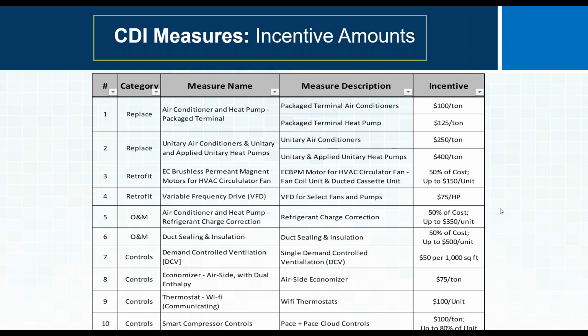The measures 5 and 6, the O&M measures, we can correct the charge on the units. One of the benefits of the PACE control we'll be hearing about is that it provides a snap diagnostic that can estimate efficiency for the unit, which can then inform the need, or lack thereof, for charge correction and other maintenance procedures. So our idea is to get some controls in the system, see how it's performing, and then see if O&M is appropriate for that unit.